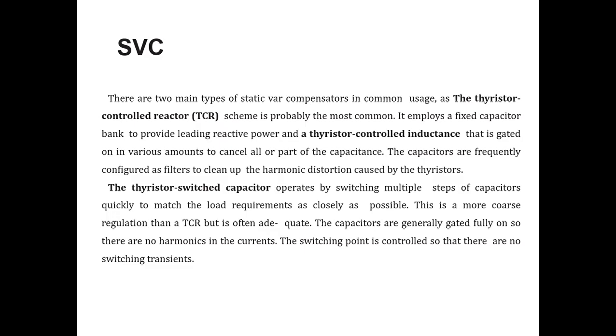When we use the thyristor switched capacitor, it operates by quickly switching multiple steps of a capacitor to match the load requirement as closely as possible. This is a more coarse regulation than the TCR, but is often adequate. The capacitors are generally gated fully on, so there are no harmonics in the current. The switching point is controlled so that there are no switching transients. So this is regarding static var compensators. Okay, so this is regarding voltage regulation and the devices that we are going to use for voltage regulation purposes. So we will stop here.